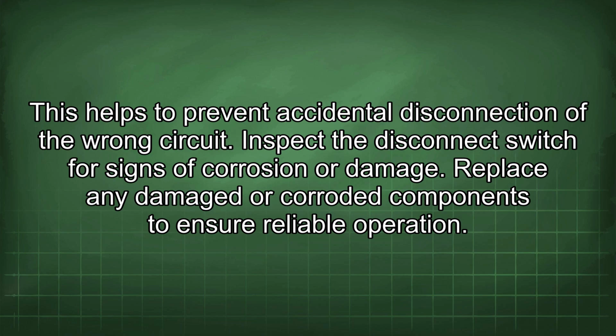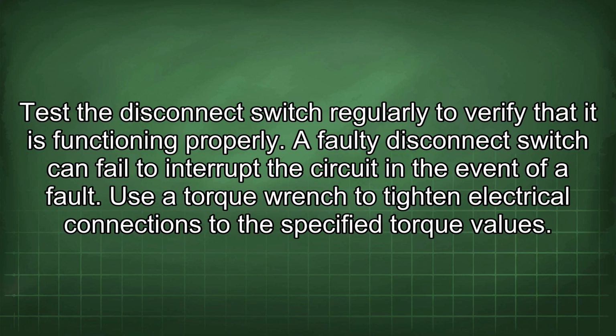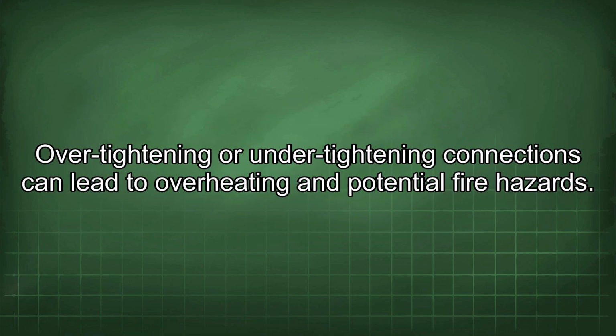Inspect the disconnect switch for signs of corrosion or damage. Replace any damaged or corroded components to ensure reliable operation. Test the disconnect switch regularly to verify that it is functioning properly. A faulty disconnect switch can fail to interrupt the circuit in the event of a fault. Use a torque wrench to tighten electrical connections to the specified torque values. Over-tightening or under-tightening connections can lead to overheating and potential fire hazards.